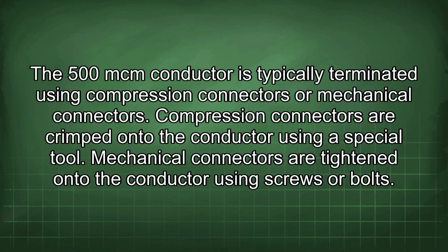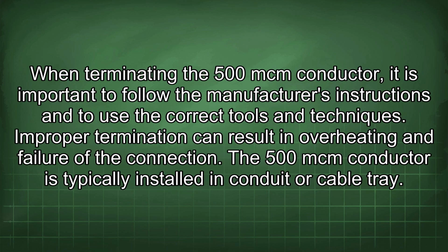The 500 mcm conductor is typically terminated using compression connectors or mechanical connectors. Compression connectors are crimped onto the conductor using a special tool. Mechanical connectors are tightened onto the conductor using screws or bolts. When terminating the 500 mcm conductor, it is important to follow the manufacturer's instructions and to use the correct tools and techniques. Improper termination can result in overheating and failure of the connection.